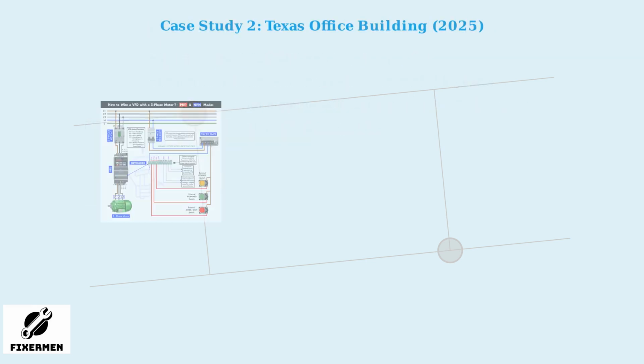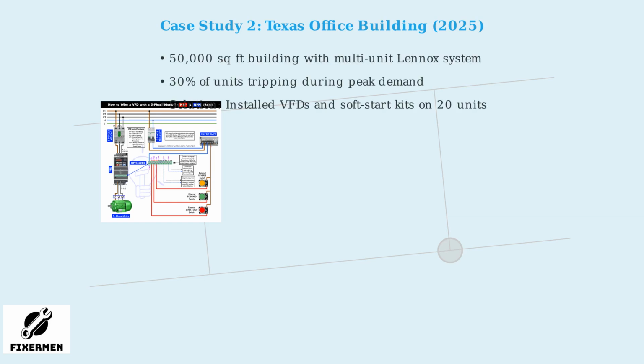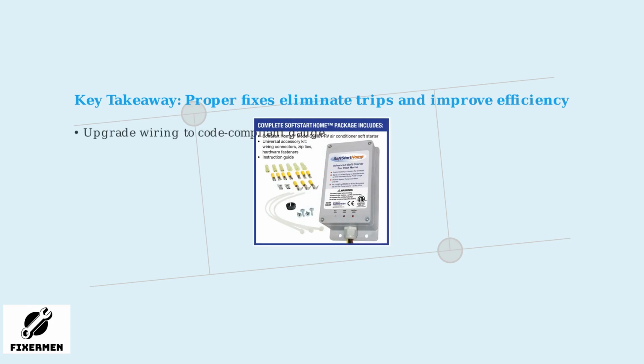Now consider a commercial example from a Texas office building in 2025. A multi unit Lennox system in a 50,000 square foot facility had 30% of units tripping breakers during peak summer demand. Lennox engineers implemented a comprehensive solution using variable frequency drives and soft start kits. These case studies demonstrate that with proper diagnosis and targeted fixes, Lennox AC tripping issues can be resolved effectively. Whether upgrading wiring for residential systems or implementing advanced technologies for commercial setups, these solutions not only fix the immediate problem but often improve efficiency and reduce long-term costs.